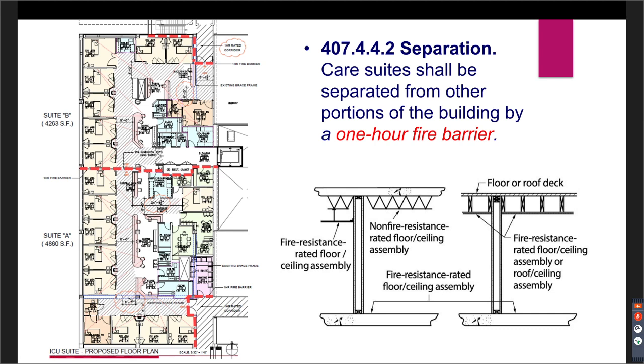One of the significant differences, and the reason I'm emphasizing fire barrier in comparison to fire partition, is how the barrier can terminate, or the section of the code that talks about continuity. Fire partitions are allowed to terminate at the underside of the fire resistance rated floor ceiling or roof ceiling. But if you see the little diagram on the right, a fire barrier is not allowed to terminate and must continue all the way to the underside of the roof sheeting, deck, or slab above.